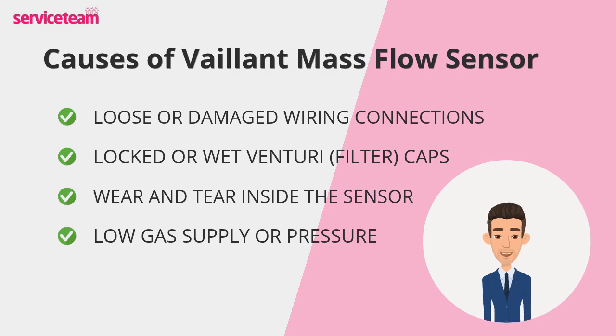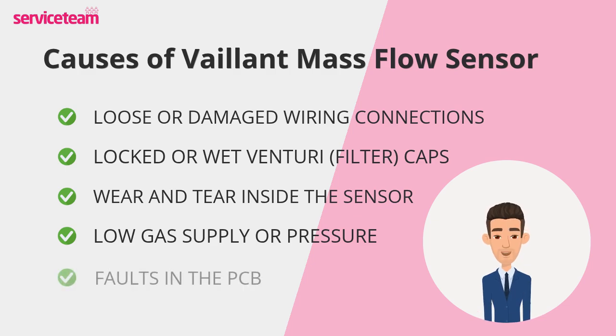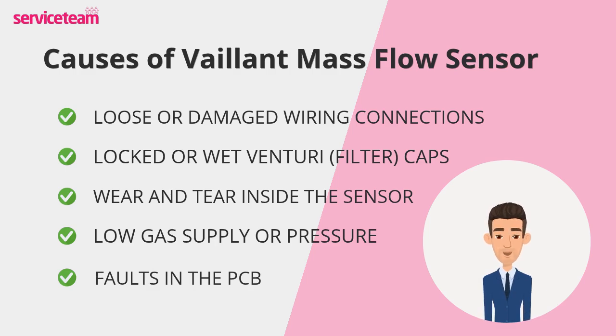The PCB relies on data from the mass flow sensor to control burner modulation. Faults in the PCB — such as software errors or component failure — can misinterpret the sensor signals. This can mimic a sensor fault and result in F52 or F53 error codes, requiring professional diagnosis to determine whether the sensor or PCB is at fault.